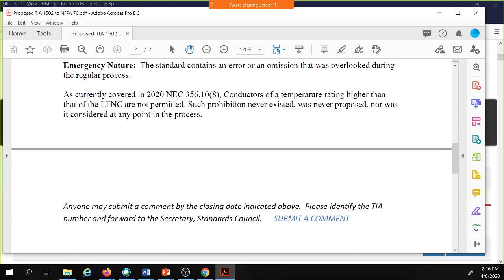And it says, as currently covered in the 2020, conductors of a temperature rating higher than that of the LFNC are not permitted. Such prohibition never existed, was never proposed, nor was it considered at any point in the process.